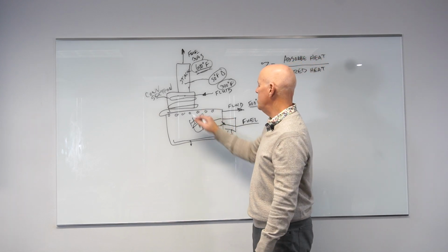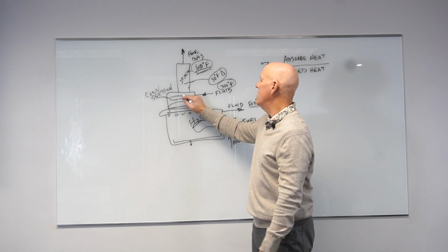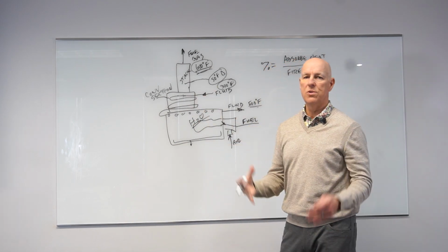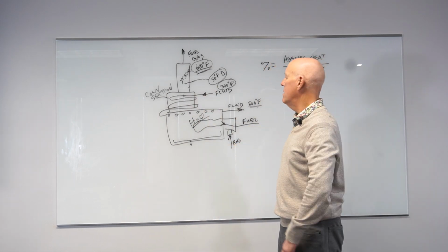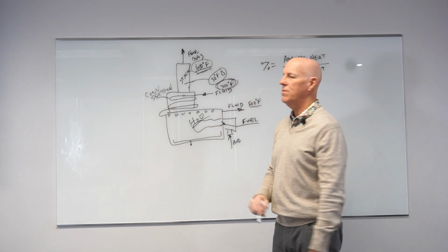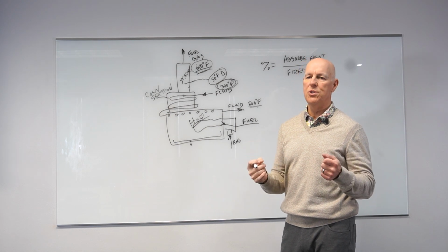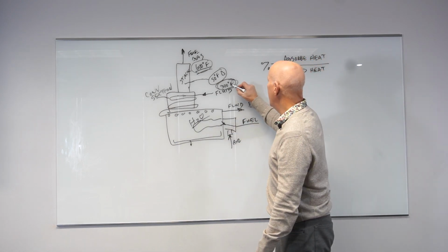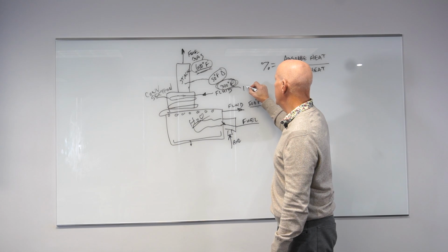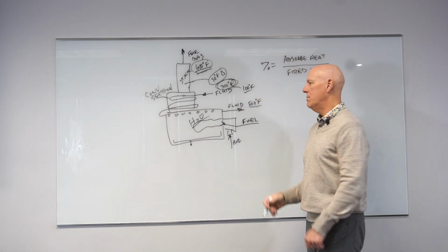So this flue gas is super, super humid. If I get down to 140 degrees or so, then I'll have condensation. Now, as long as this is 300, I can't get to 140. So really, the condensation issue is only relevant when I have a really low inlet temperature, let's say 100 degrees F. Then I've got condensation I've got to think about.